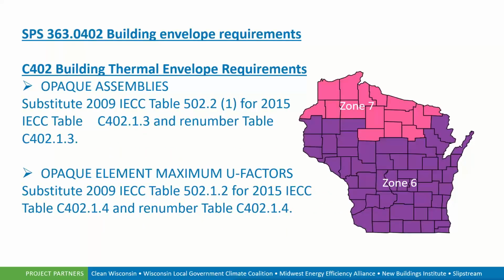C402 talks about building thermal envelope requirements. We know the state has 2 climate zones, Zone 6 and Zone 7. Now, when we look at the code, as the 2015 IECC stock code is written, the tables have been changed and renamed. They were substituting the 2009 IECC table 502.2(1) for the C402.1.3 table as it existed in the 2015 code, published in the 2015 code. It's also renumbered to that same section, table number C402.1.3.